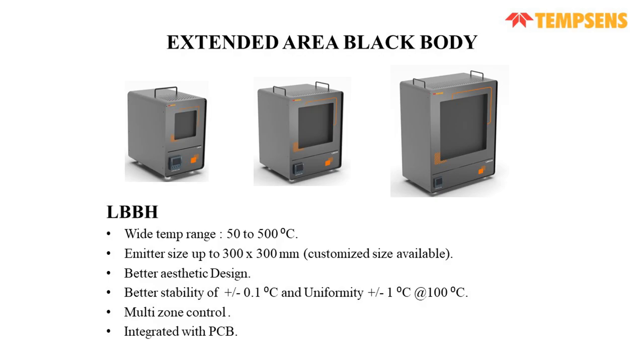Then we have LBB H models. So H models have a temperature range of 50 to 500, and the emitter size is available up to 500 by 500. It is written here 300 by 300, but recently we have supplied 500 by 500 emitter size as well. It has a better aesthetic design, better stability of plus minus 0.1 degree, and uniformity of plus minus 1 degree at 100 degree. As the size of the emitter increases, the multi-zone control comes into picture. So it has multi-zone control.